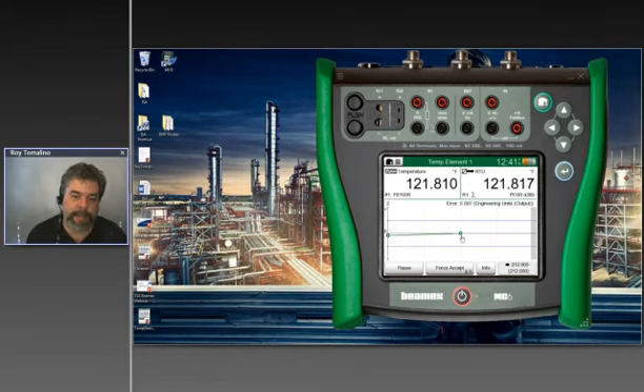So it's just grabbed our middle test point, and we can see that, boy, that's right on the zero. We're at our midpoint, there is relatively no error. The tolerance that I have on this is a rather large 1 degree Fahrenheit, plus or minus. So that's what the blue dotted lines represent. If my temperature were outside of that 1 degree error, then it would turn red like you're seeing on the screen right now. And while that's going on, let me show you another example of what you might do in an autoclave scenario.